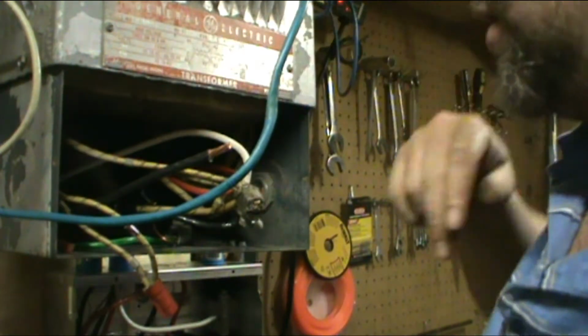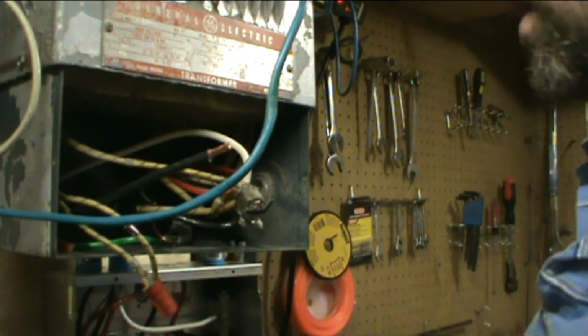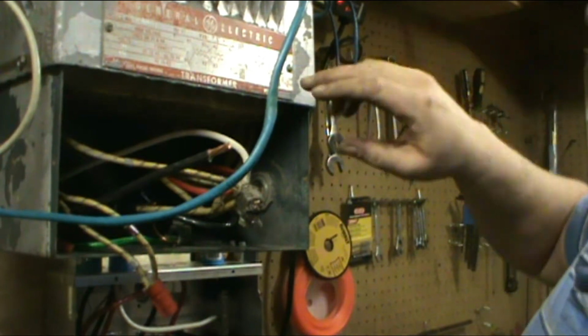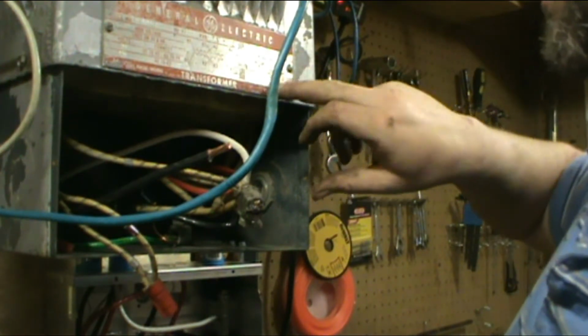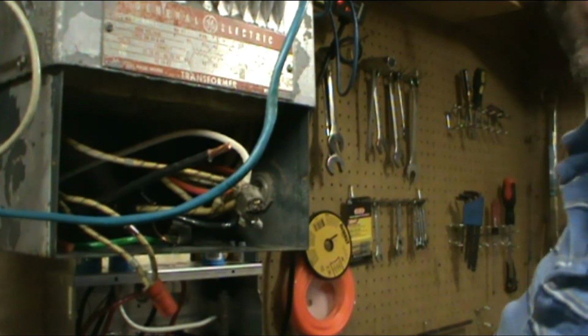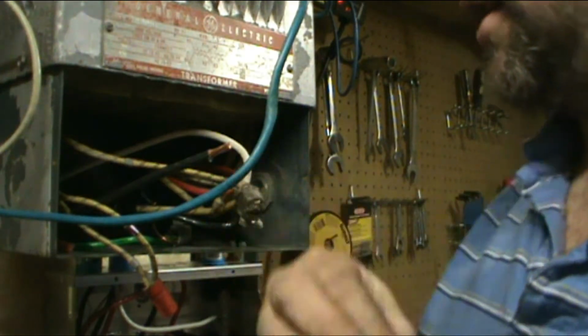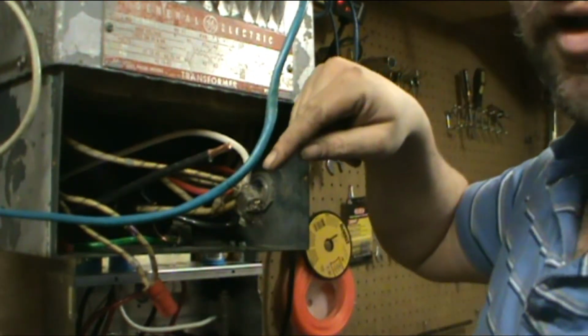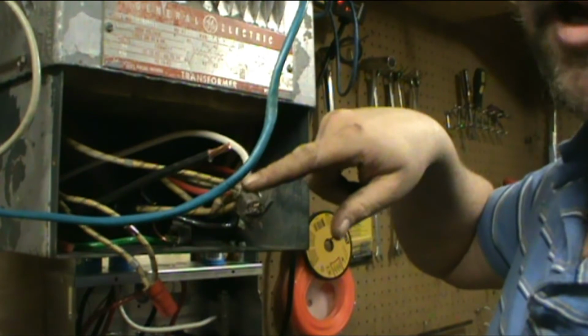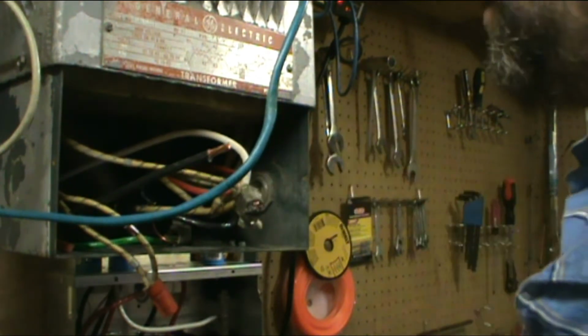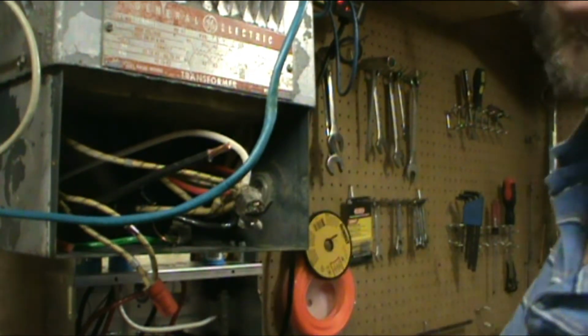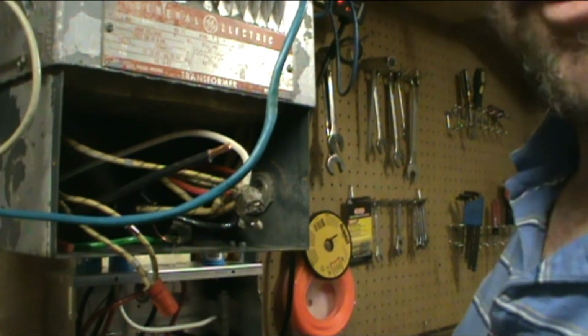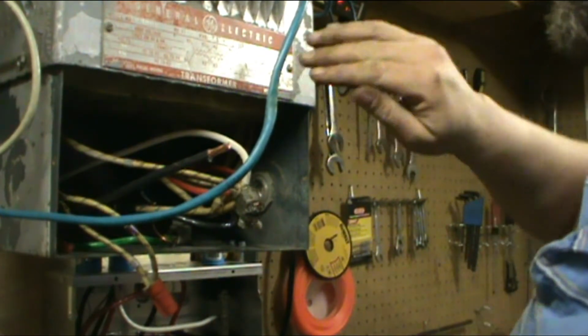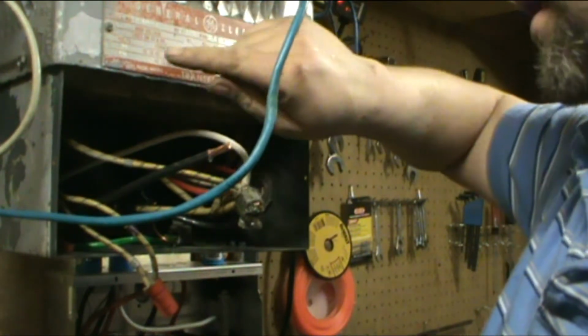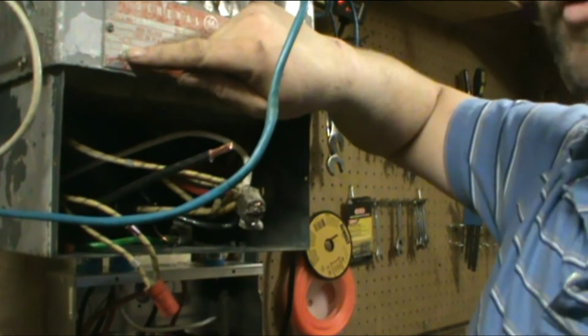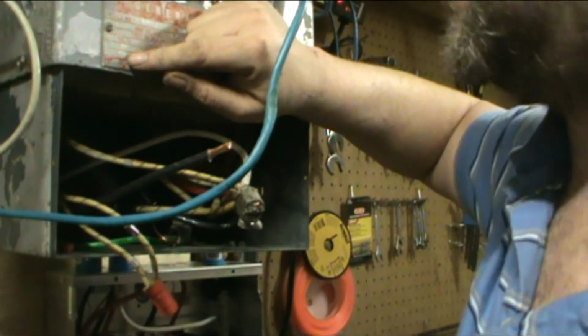There's a diagram on here that shows you exactly how to wire that up. Alright, on the low side, I've got X2, X3, they're wired together. And then they're going to this lug right there. See, I can actually touch it. Yes, it's live. There's 240. If I touch that and touch that, probably knock my... Yeah, it wouldn't feel so good. But so now we're going to step that up. And I want 240 volts. Actually, I can go 240, 480, but we don't want 480 on the output.